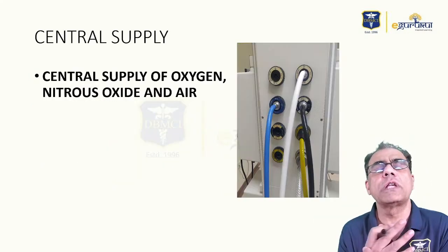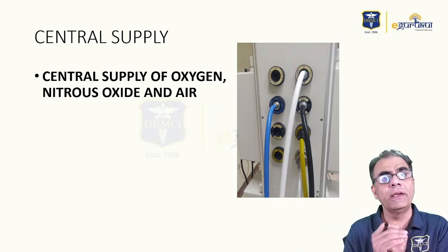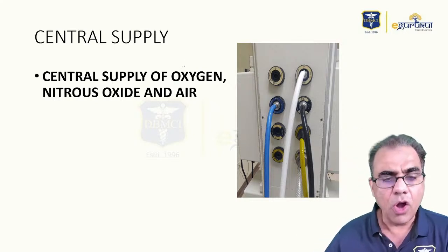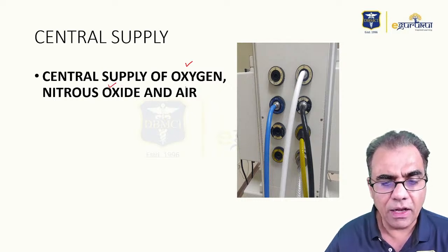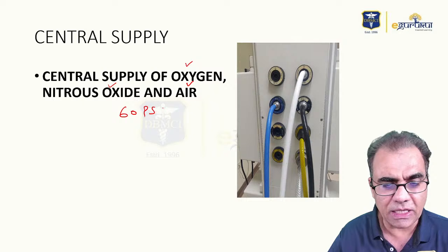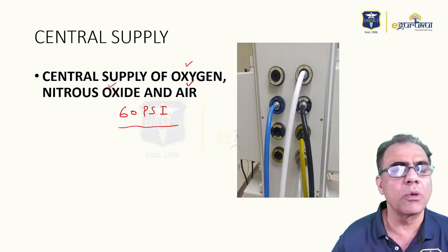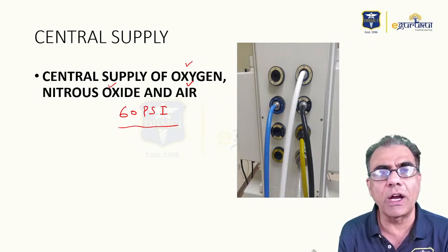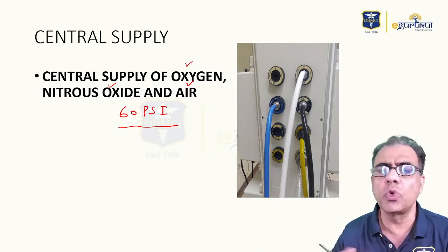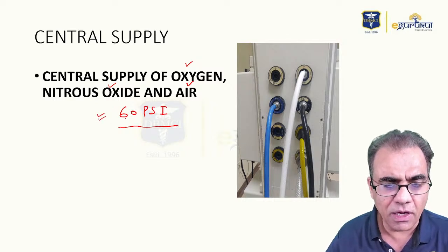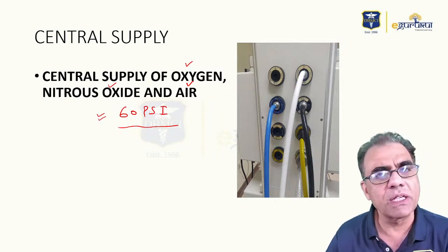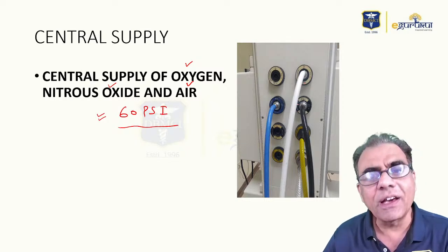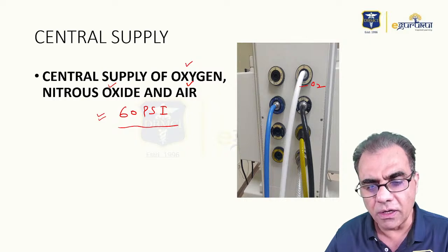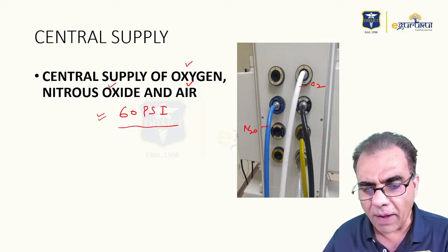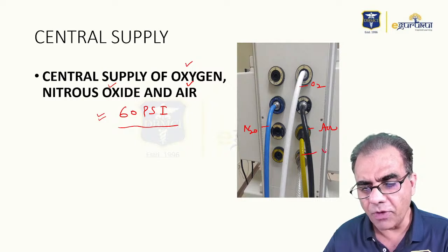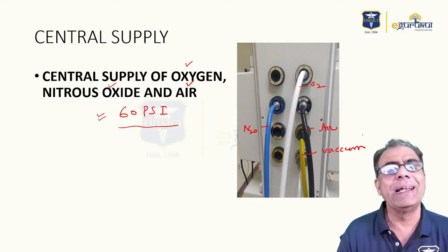Not only through cylinders, gases are also supplied through central supply, and the central supply of oxygen, nitrous oxide, and air is at a pressure of 60 psi. In your books, you may find different answers because in the US it is supplied at 50 and in the UK at 55, so depending on the source they have given the answer. However, in India, the central supply is at 60 psi. The pipes have different color codes. A white pipe is for oxygen, a blue pipe for nitrous oxide, a black pipe for air, and a yellow pipe for vacuum, or central suction.